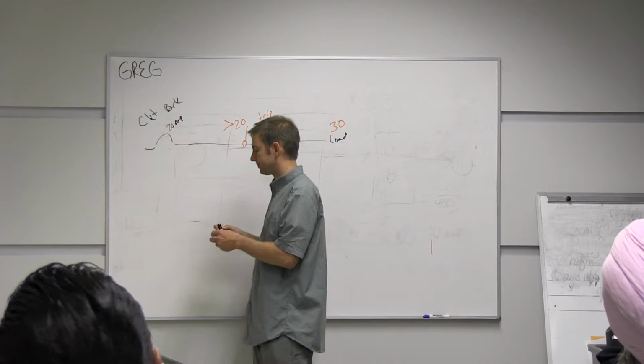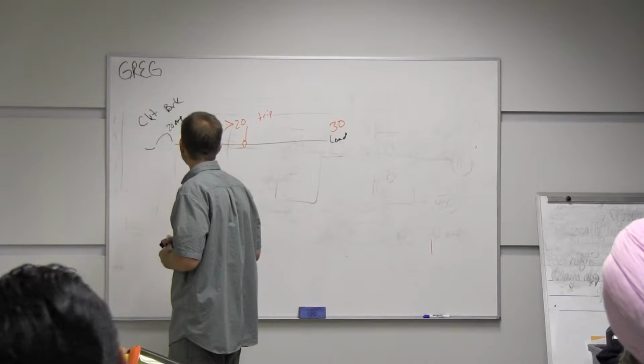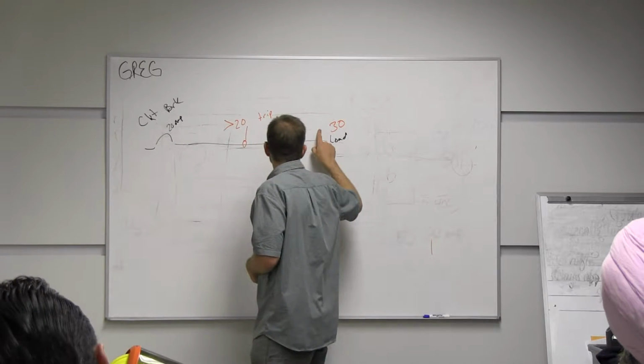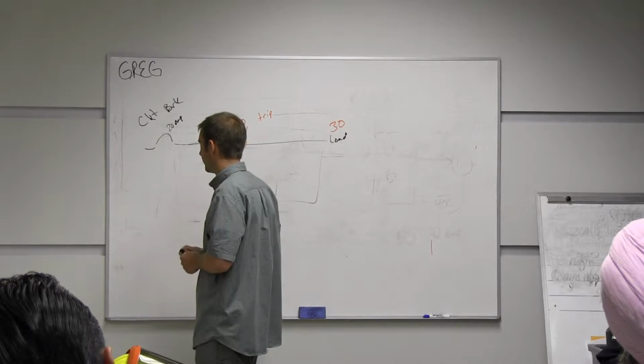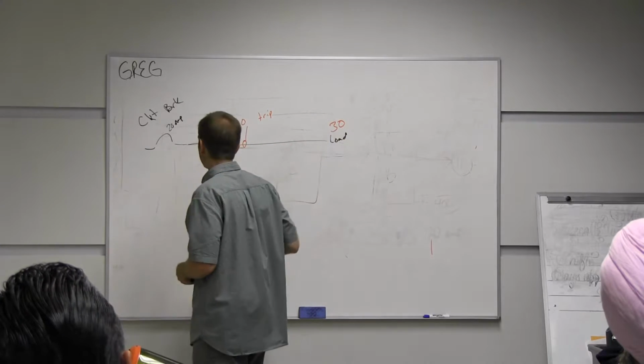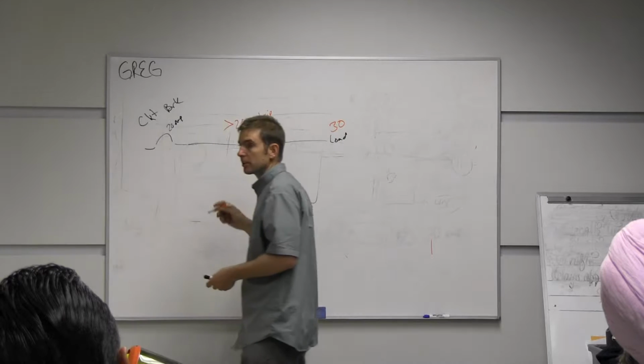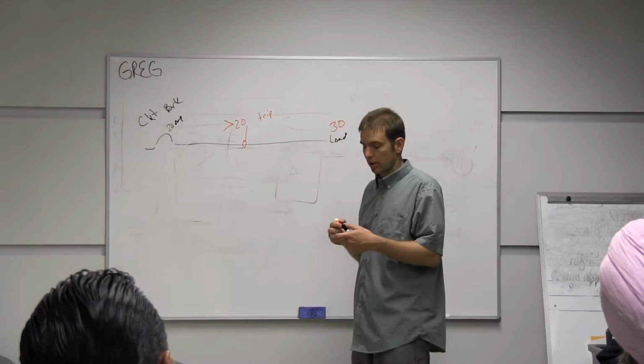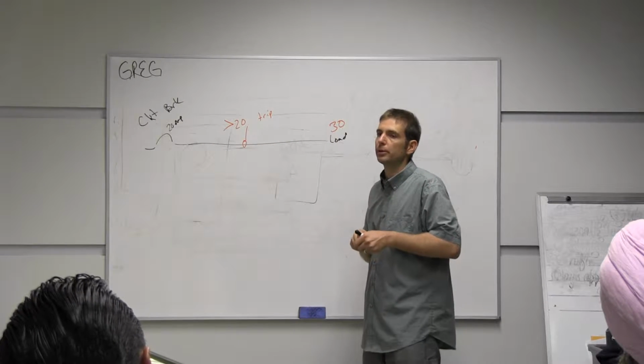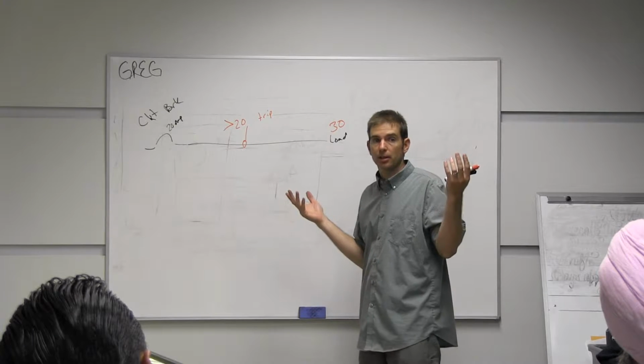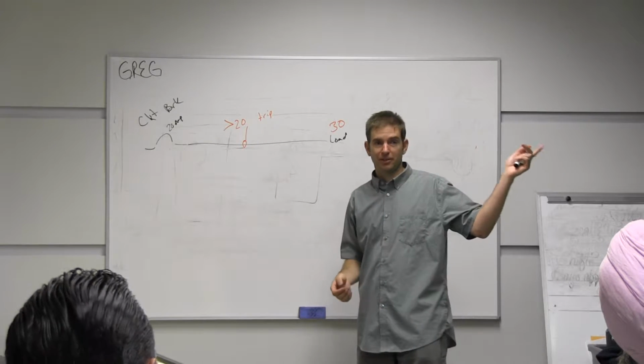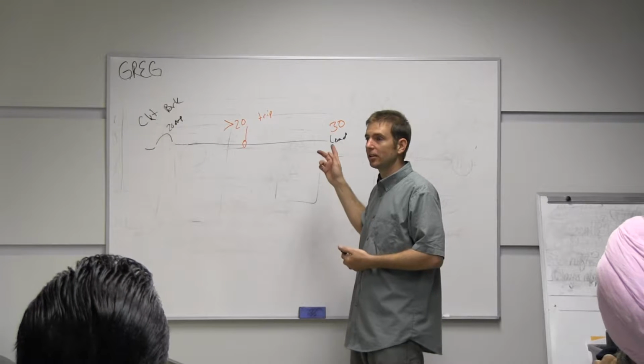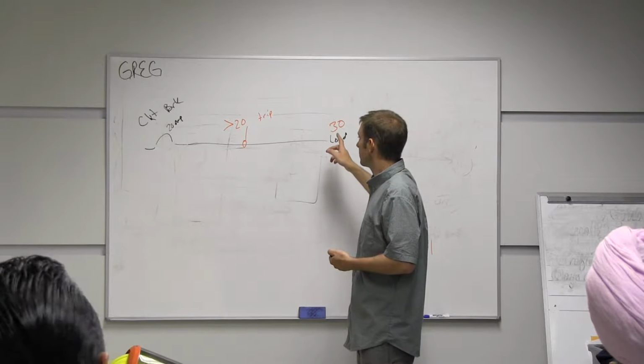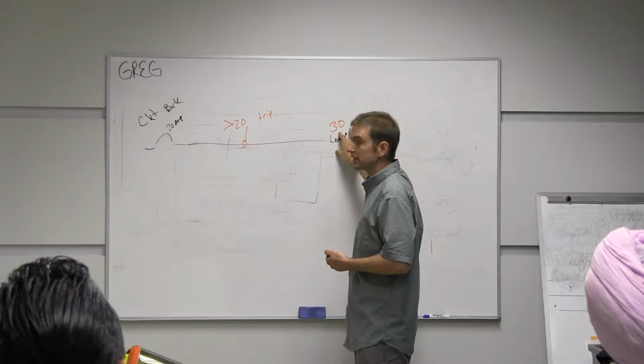Yeah. In fact, for a continuous load, whatever your load is, let's say your lighting circuit is 30 amps. A continuous load is a load that operates for more than 3 hours at a time. So we have our lights on all day. In fact, we have this TV on all day, right? But we have our lights on all day, and that's considered a continuous load.